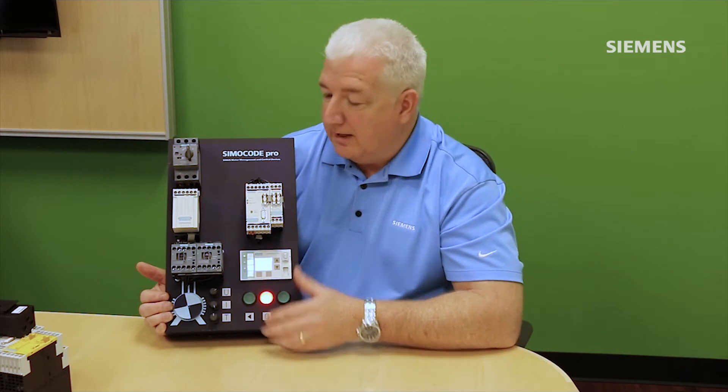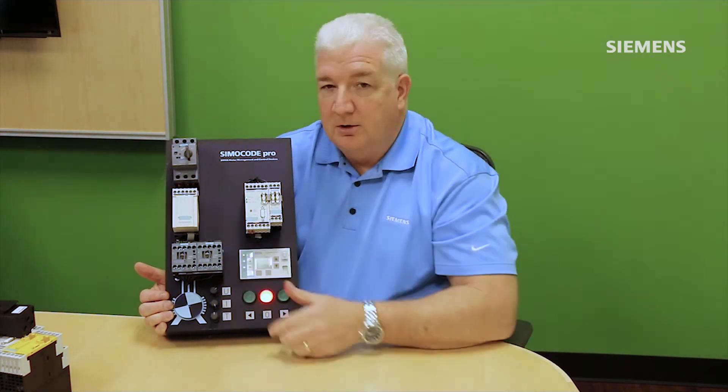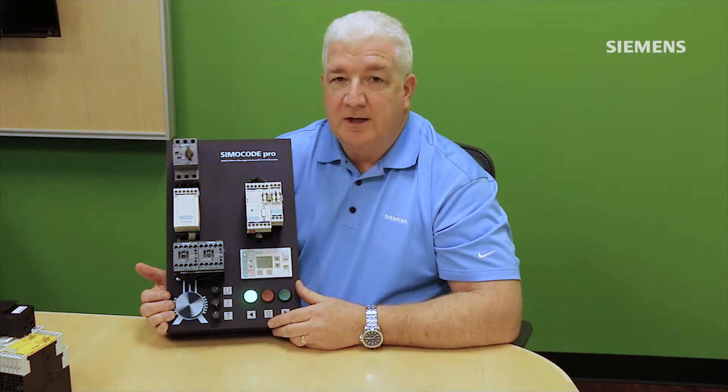In addition to the I/O function, SIMOCODE also offers a tremendous amount of monitoring capability. Not only will it protect the motor, but you can measure and monitor many different conditions. Using the current and voltage measuring module, if normally my motor is running at 8 amps and something changes so it's now running at 9 or 9.5 amps, I can set different threshold values inside SIMOCODE to annunciate a warning or a shutdown condition based on that change in dynamics.